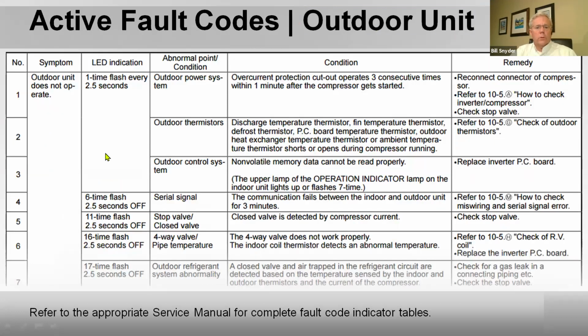Okay, outdoor fault codes. You've got symptoms here, and it gives you the abnormal point. Outdoor thermistors tells you the condition that might be happening and maybe the remedy, what to do. Replace the inverter PC board, for instance, in this case. And these were all 1-time flash every 2.5 seconds. Could give you any of these 3 things to look at. So make sure you look at the service manual for the complete fault codes for the specific piece of equipment you have. This information I'm showing you here is for one particular piece of equipment.